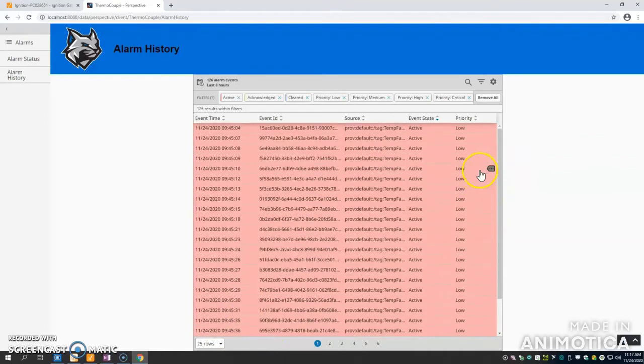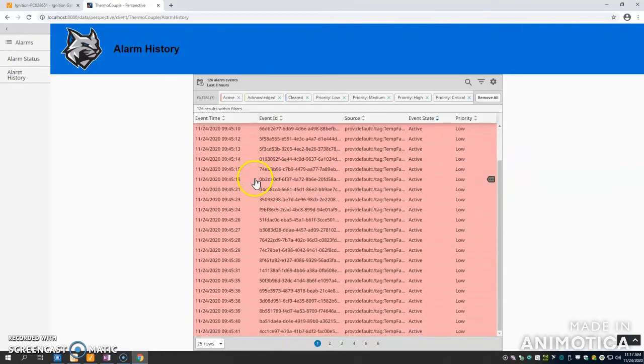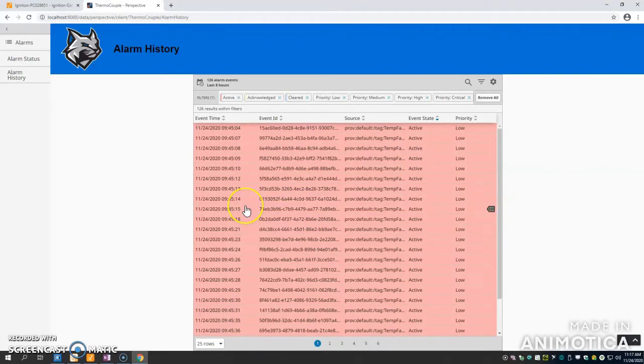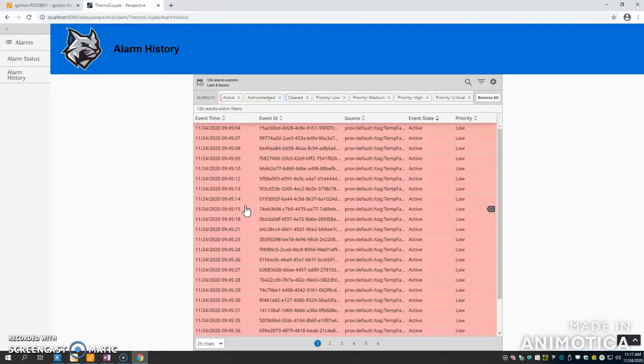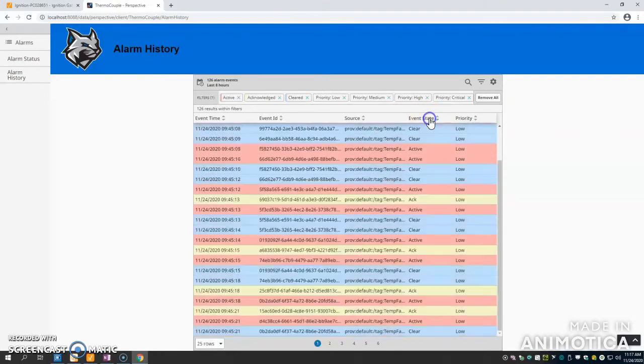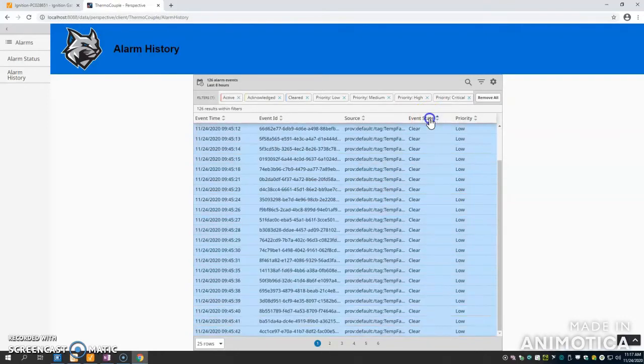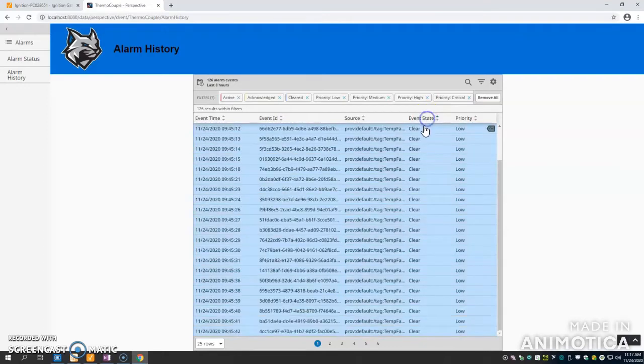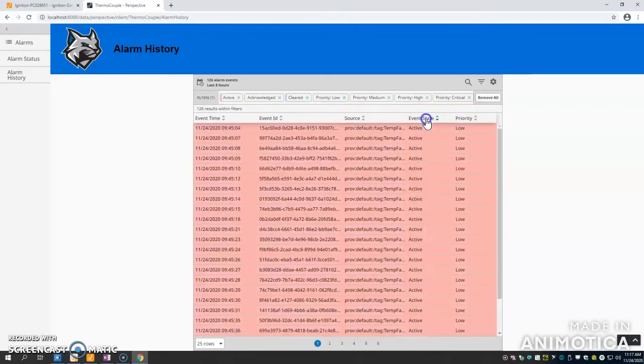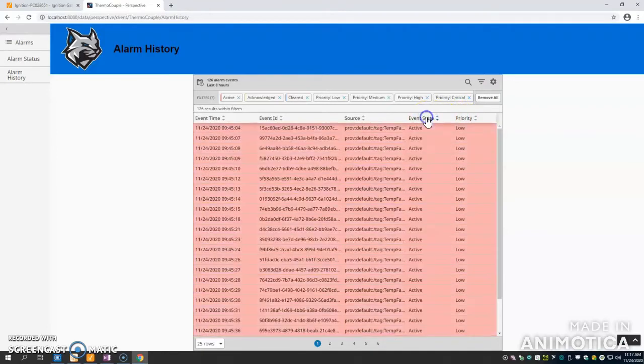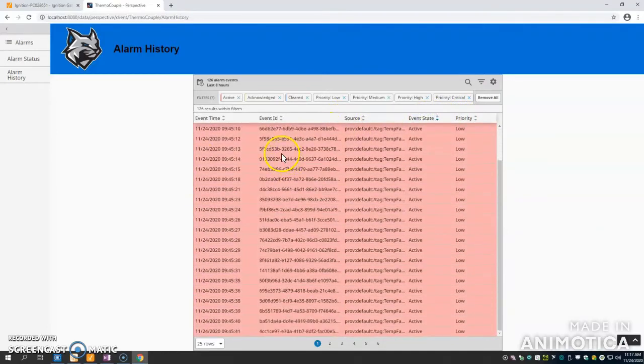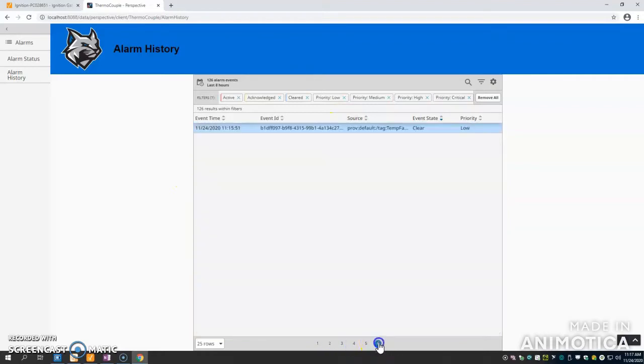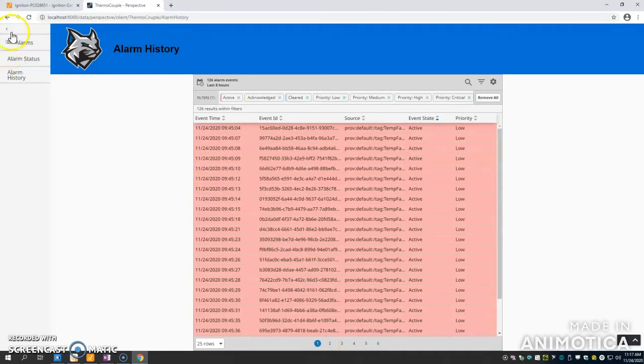There's data pruning, so it'll get rid of data after a certain amount of time, if it's a year, two years, whatever. You can partition it, you can do all that. It's super powerful software. It will go back large stretches of time. Obviously, right here, it's just short because I didn't have the PLC hooked up before this morning, but it'll show everything, which is super powerful and useful. Being able to look at alarms from months or years ago to see patterns so you can make smarter systems is definitely important.